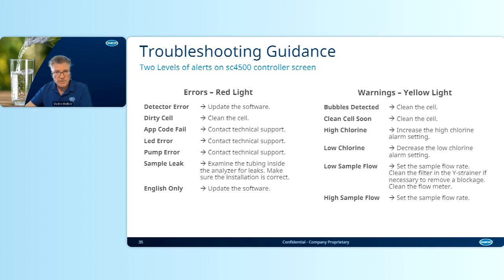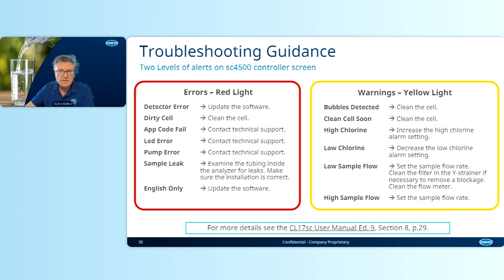Now, when everything is done right and something goes wrong anyway, there are 2 levels of alerts presented on the SC controller screen. The errors and the warnings are different by color. And you can see very clearly from far away that for errors the light is red, the screen is going to be red. What is important to remember about red light is that it's an error message and it's an alarm, and the instrument is not operating. It's waiting for immediate attention.